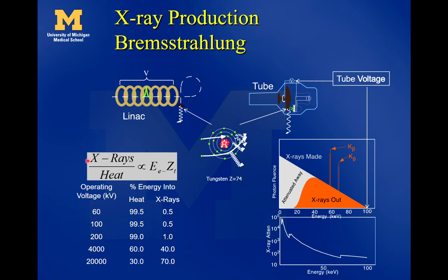We have a simple equation for x-ray production. The ratio of x-ray production versus heat production is proportional to the energy of the accelerated electrons crashing into the anode, multiplied by the atomic number Z of the target material. So if we use higher-Z materials — for example, tungsten has a Z of 74 — we get better x-ray production. If we ramp up the accelerating voltage of the electrons, we'll get more x-rays produced instead of heat.